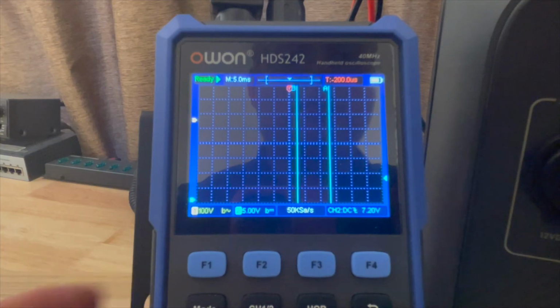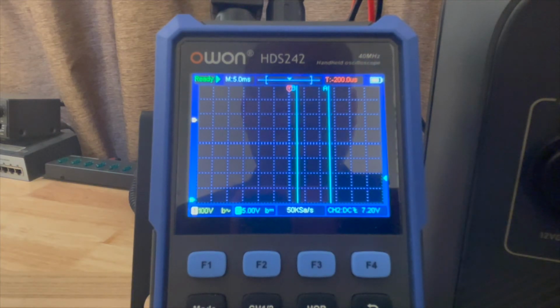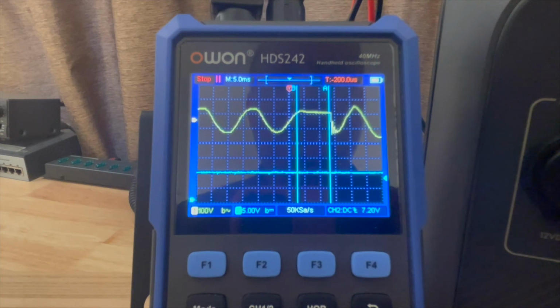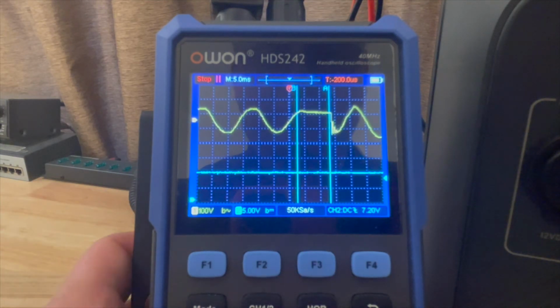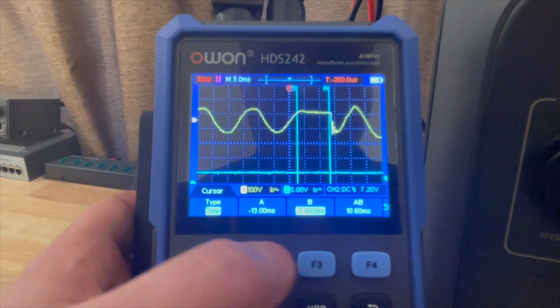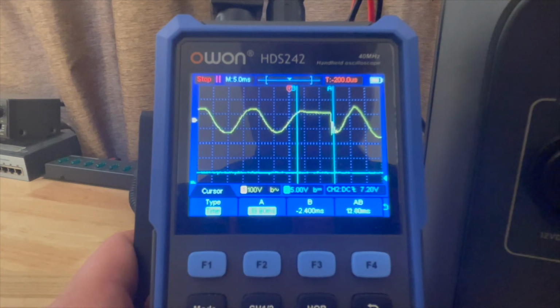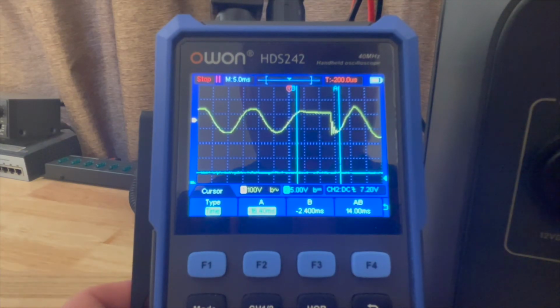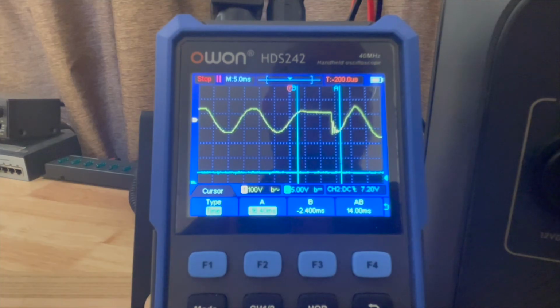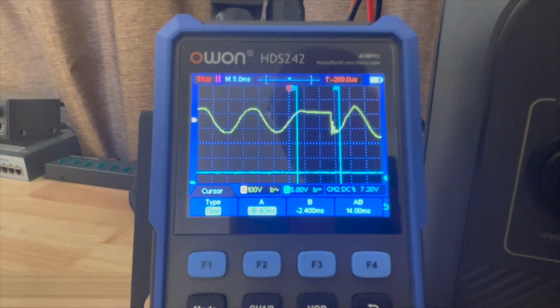Okay, we're charging again, let's cut it off a third time. This time lasted a little longer, so it's good to actually measure. At the end of that squiggle there, that's about 14 milliseconds. So it's a little bit longer than 10 milliseconds, but still within range. We're definitely within the 20 millisecond range.